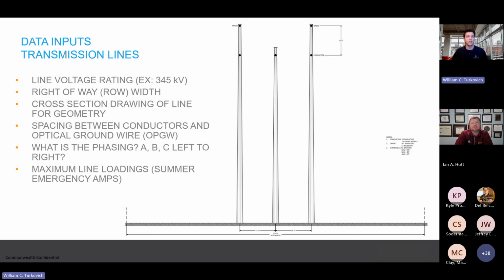The next one might be a little harder to find out: how far the easement or right-of-way width is. In this picture, you can see it's 125 feet across. The next is the geometry of the poles and where the conductors are relative to each other, relative to the ground, relative to the optical ground wire above them.